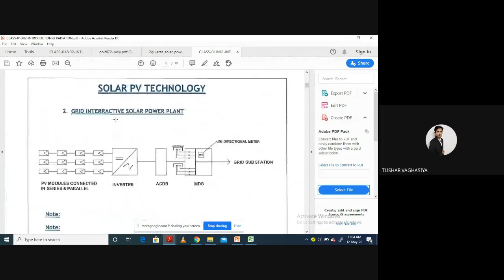But here we do not have multiple strings in the industrial power plant. If it is a maximum of up to 500 kilowatt, we can say 700 kilowatt, there are multiple inverters. So here we are using an inverter with multiple MPPTs, and we are not using the string combiner box. We can give directly from the module to the inverter, and it converts into AC. We put an ACDB here for combining all this supply, and for the protection of the inverter also.